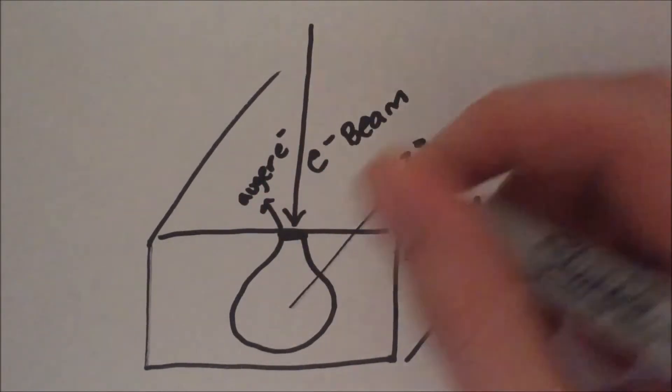This sample volume is teardrop-shaped and is the place where backscattered and secondary electrons are generated, as well as visible and X-ray photons. This interaction volume can be as deep as 5 micrometers depending on the beam energy.